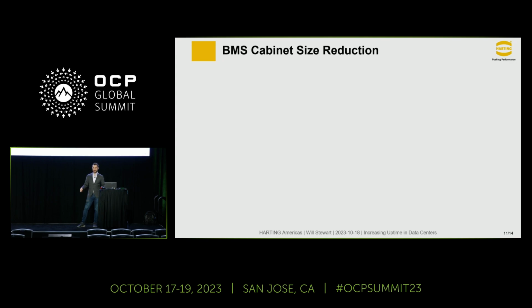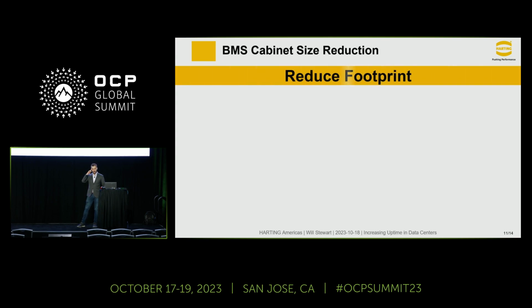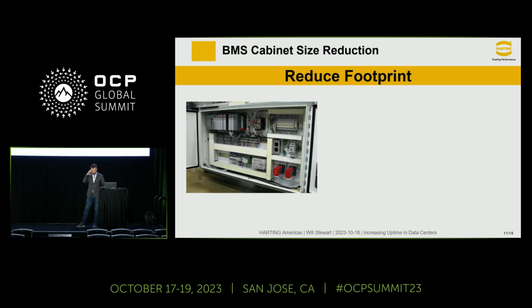Another example, going back to the BMS cabinets — I talked before about putting M12s on it to get to market faster. Another component of the PLC cabinet is the fuse terminal block you can see up there. If you have a PLC, you're required to have a fuse or circuit breaker to protect it, because PLCs cost tens of thousands of dollars, whereas a fuse costs $1.